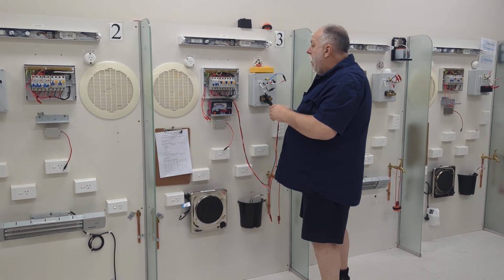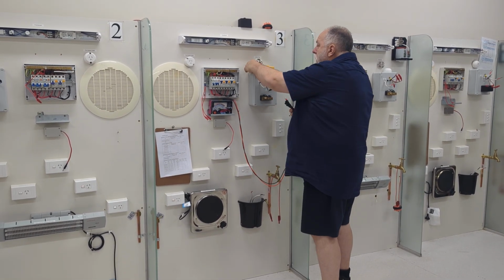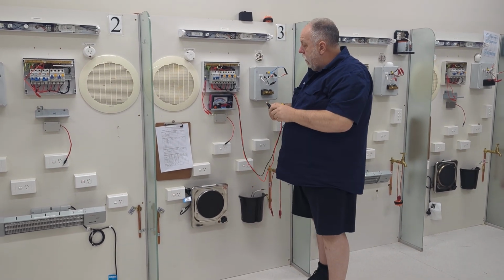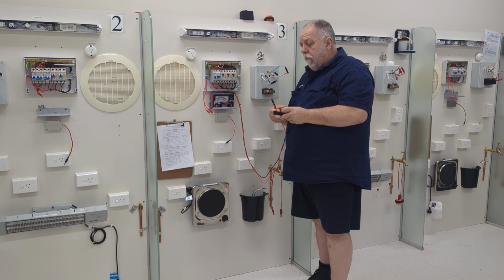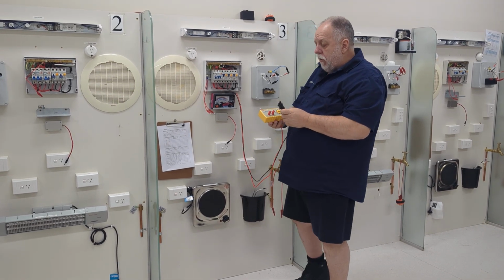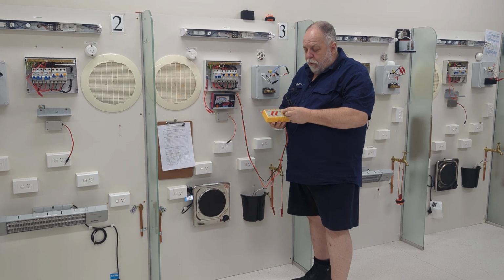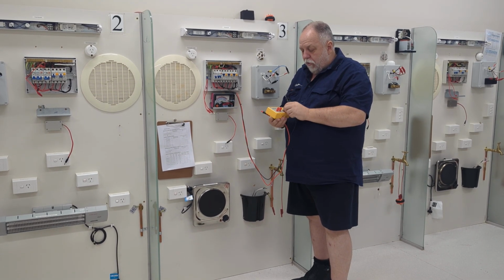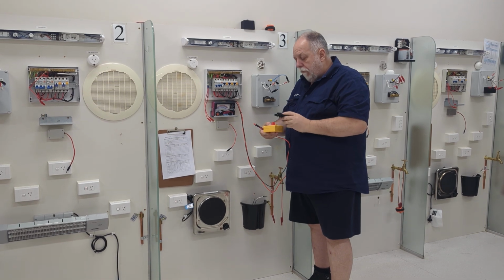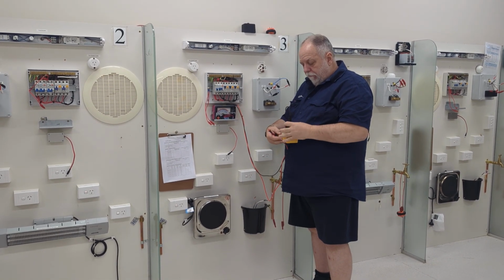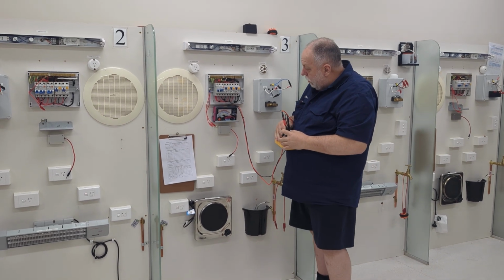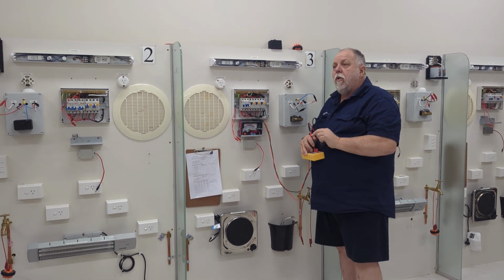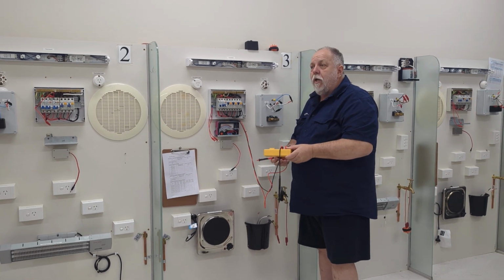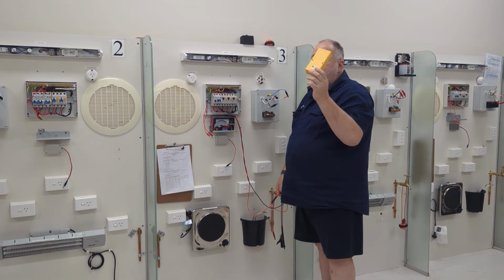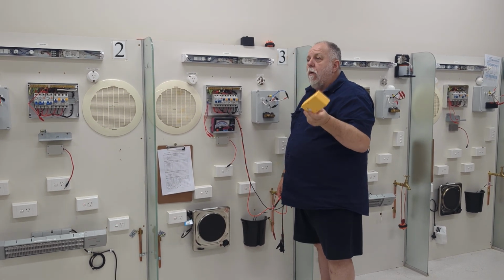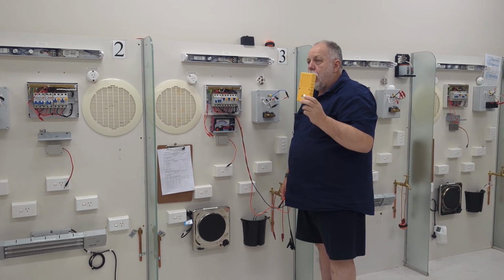So I've got to that point. When I push it in and I've got the 500 volts, if I short the leads together, it goes back to 0. That's okay. But we also use something like this, what we call an insulation tester checker. It's basically putting the voltage under load. So if I go to 2 meg or 1 meg on here, I can put that across my load, all right? And it should come up to 1 meg, all right? So it's putting it under load, making sure you don't grab the leads yourself and get a whack. Instead of 0 on the meter, we use this to actually load it down, and check that what I'm reading under load is correct on the meter. Are we all good with that? All right?